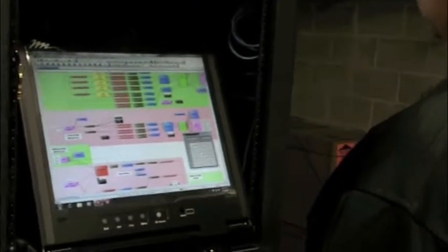And whenever that signal is activated, let me show you what it looks like when it's activated. So all other input is muted if it receives a signal that the fire page has been activated. And that input, for those of you who are interested in signal flow, only activates input 8. Input 8 is your fire page, and it feeds via CobraNet to the other systems.